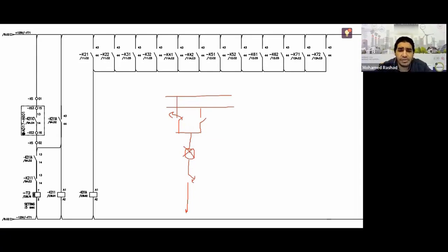So what will happen if this closes? An arc will occur on whose terminals? It will explode. All right, so I gave a close command to this disconnector, and at the same time, I gave a close command to that disconnector. It was a quick action, like sitting at the computer and giving a close command immediately with one press. These two blades close together as if you have coupled between the two bus bars, meaning you are passing current through it. I will also talk to you about its interlocking, but these two will explode.